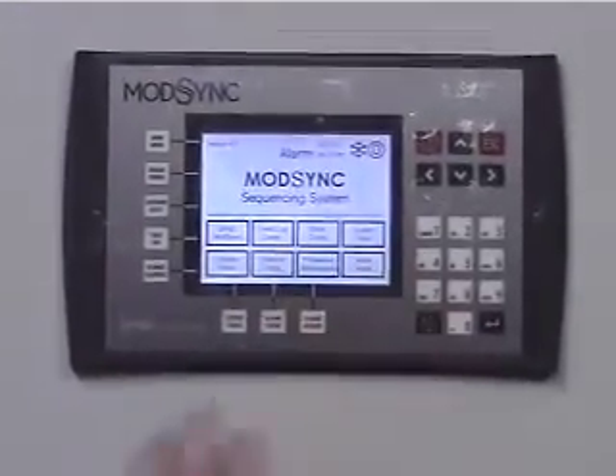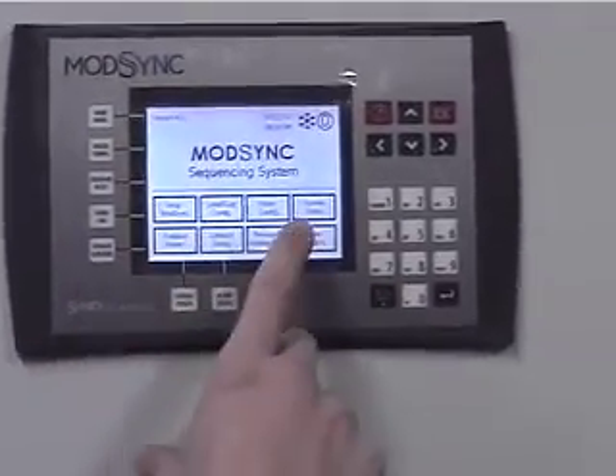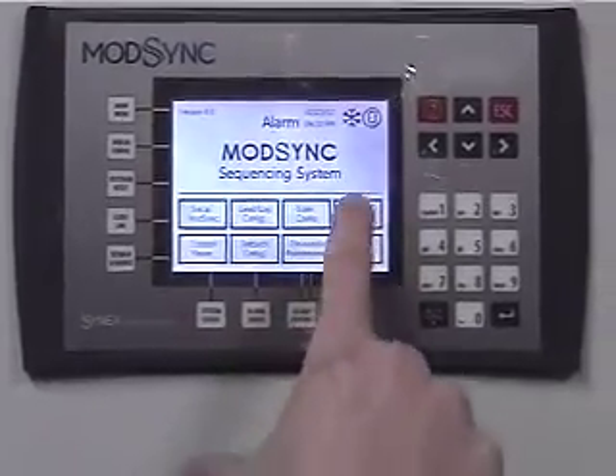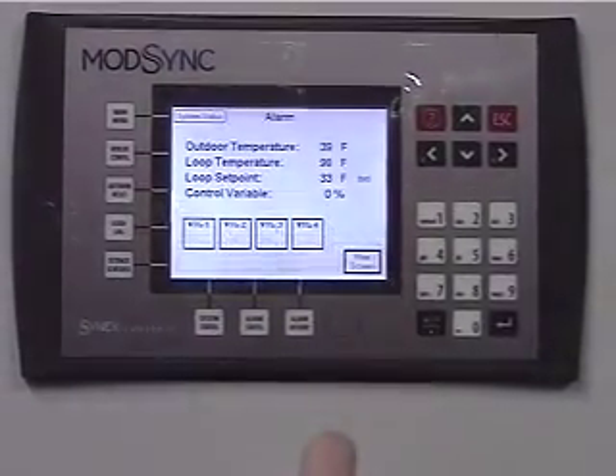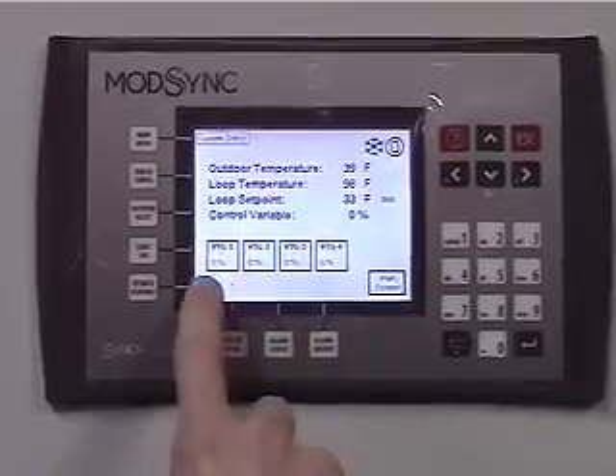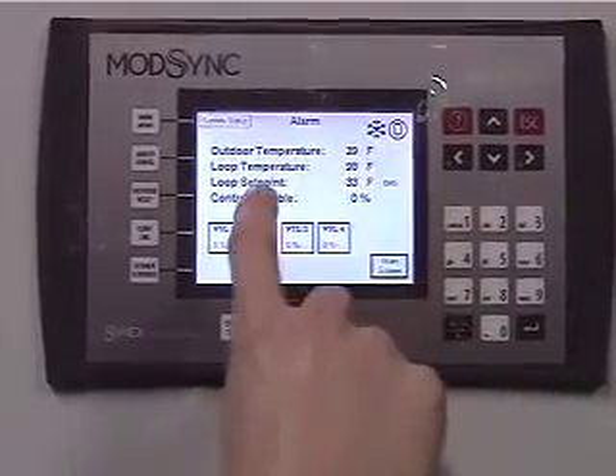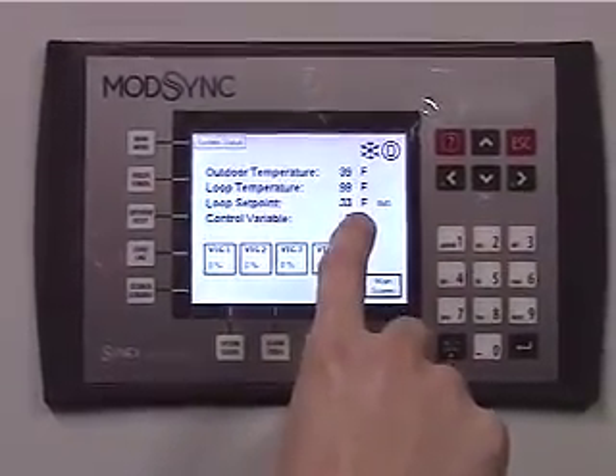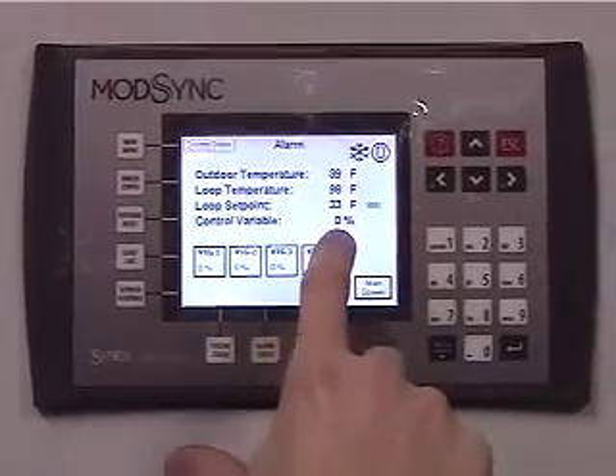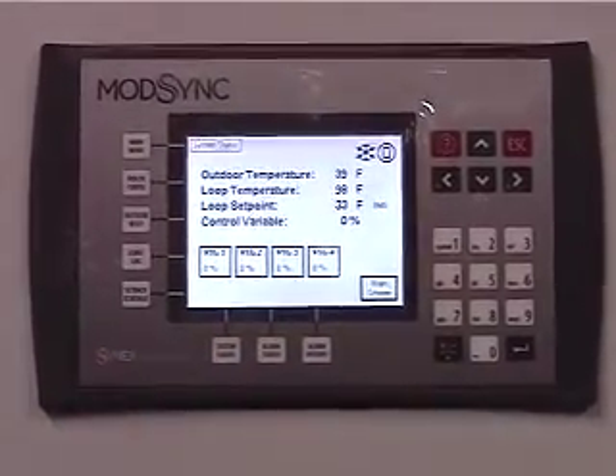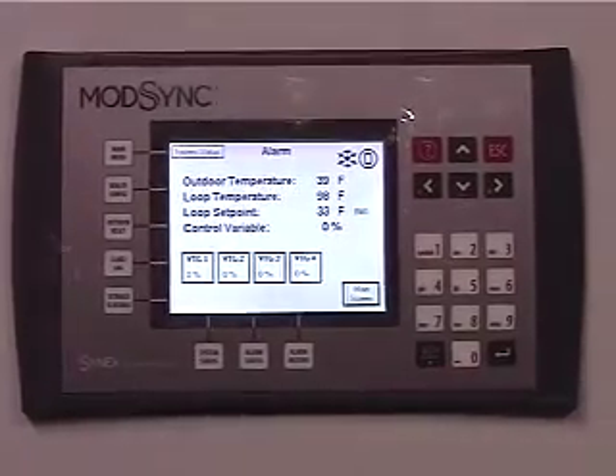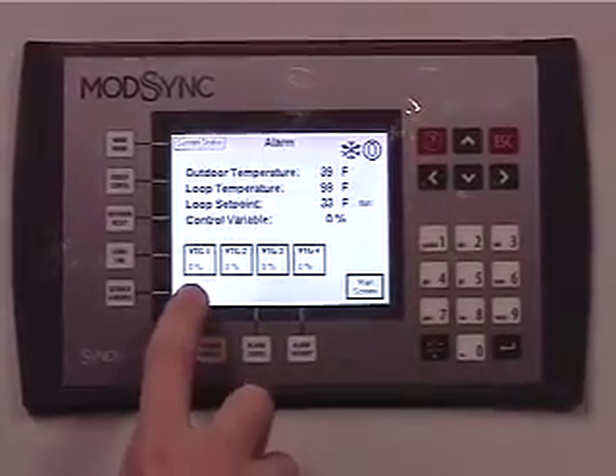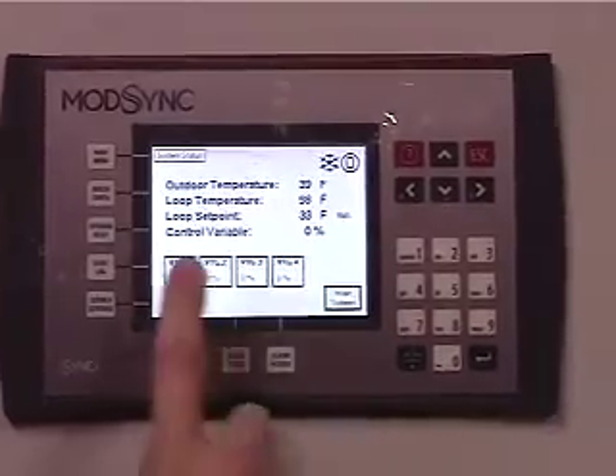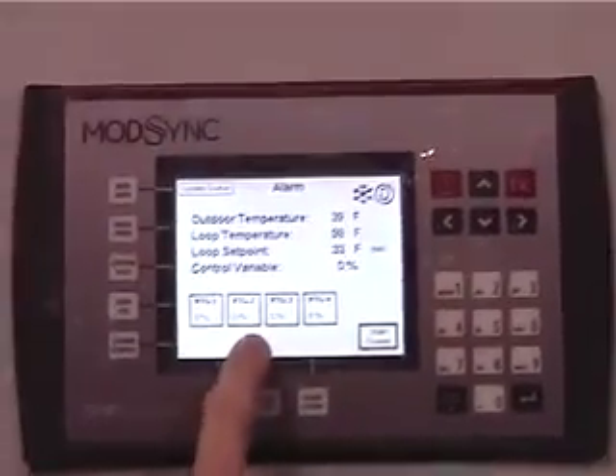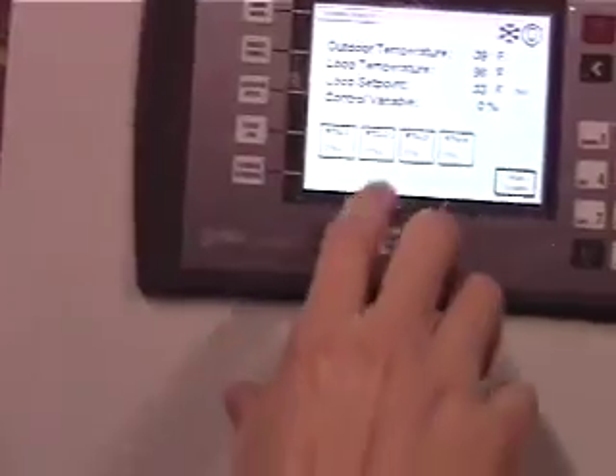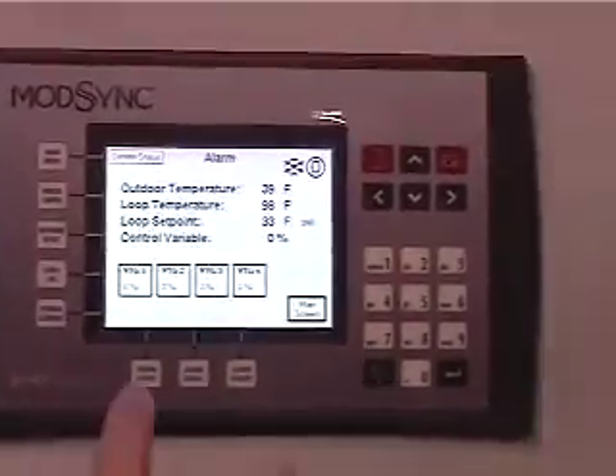You can look at this and say, okay, I'd like to check my system status. It shows your 4 boilers, and it shows that there's no call, your outdoor temperature, your loop temperature, your set point, and then your control variable. The control variable is the control that it's going to be sending to the boilers to get them on. This controller is not going to drive one boiler up to 100% with the others off. It'll drive it up to about 60%, then bring the second boiler on, take those to 30%, and so on. Go up to 60 and then bring on the other.